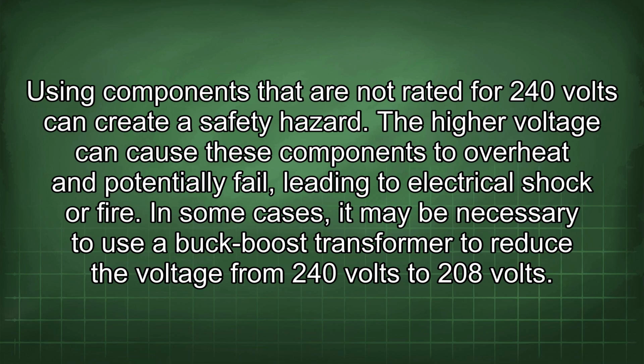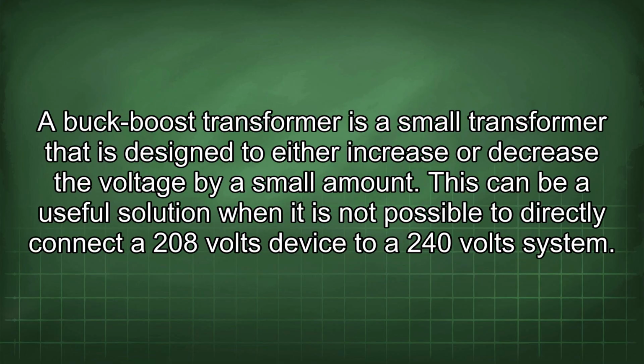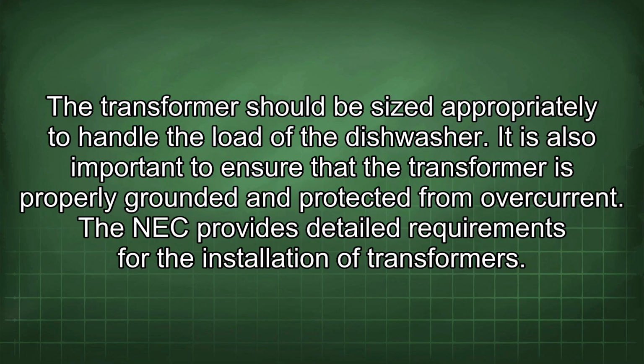In some cases, it may be necessary to use a buck boost transformer to reduce the voltage from 240 volts to 208 volts. A buck boost transformer is a small transformer that is designed to either increase or decrease the voltage by a small amount. This can be a useful solution when it is not possible to directly connect a 208 volts device to a 240 volt system. The transformer should be sized appropriately to handle the load of the dishwasher. It is also important to ensure that the transformer is properly grounded and protected from overcurrent. The NEC provides detailed requirements for the installation of transformers.